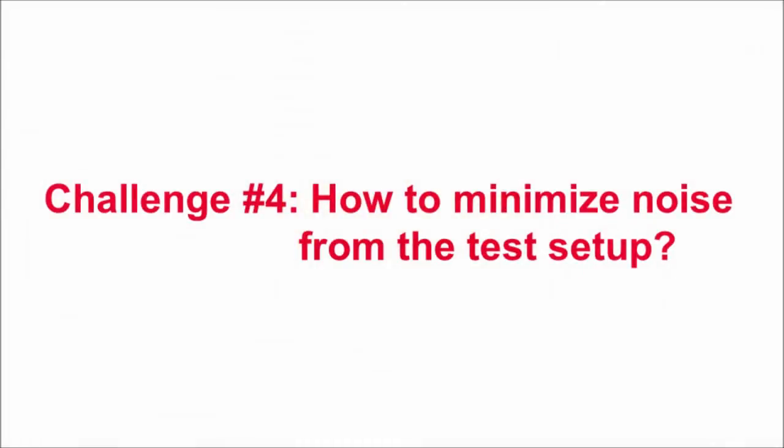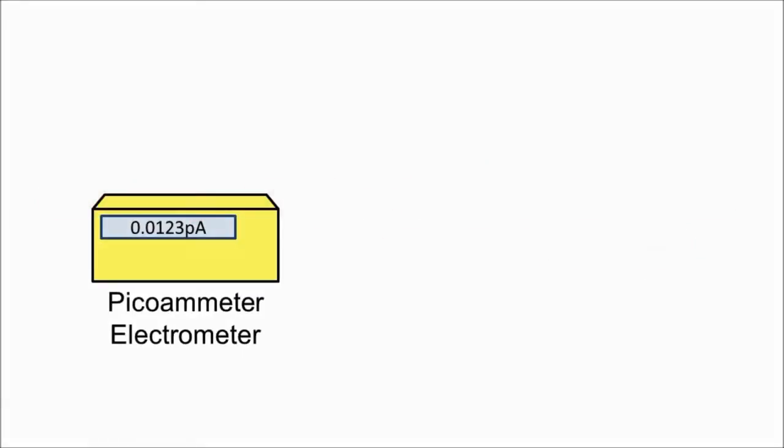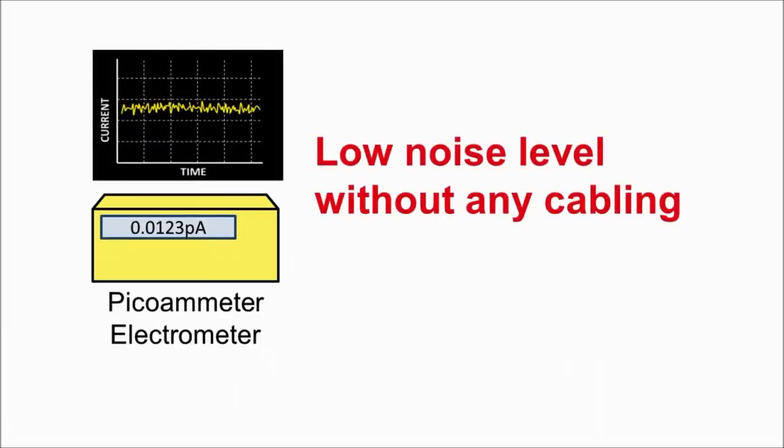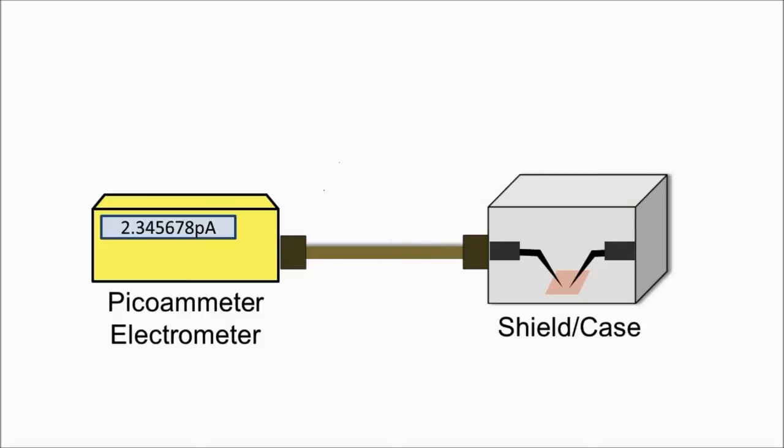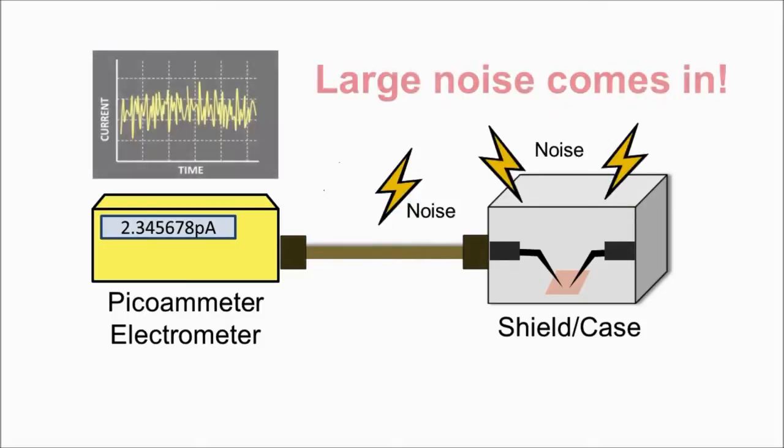Finally, even if your instrument is properly configured, your measurement setup can introduce significant noise through its cables, connectors, and chambers. However, conventional instruments do not provide any means to isolate the noise sources.